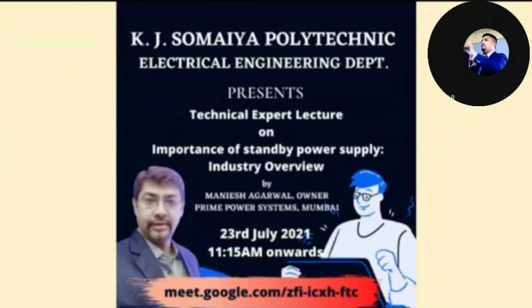Add one point here. Nowadays, with this pandemic going on, hospitals are having this issue of oxygen supply. If anything related to electricity goes down, in such kind of emergency supply which we talk about, it's not about the power, it's about the purpose of that power. The purpose for which we are using this standby power supply is to have a continuous power supply. And that is why we are looking at the DG set not from the point of view of a conventional or a non-conventional energy source.